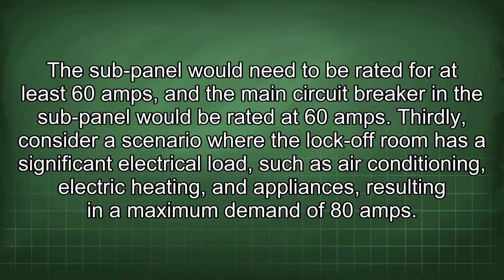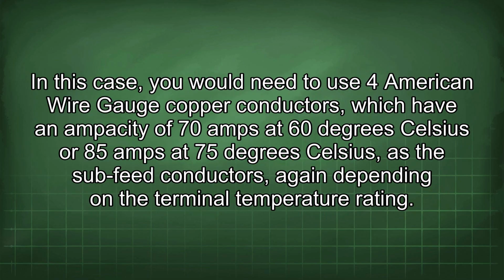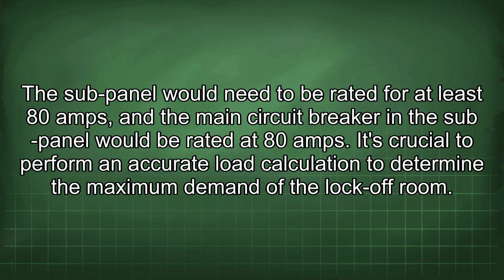Thirdly, consider a scenario where the lock-off room has a significant electrical load, such as air conditioning, electric heating, and appliances, resulting in a maximum demand of 80 amps. In this case, you would need to use 4 American wire gauge copper conductors, which have an ampacity of 70 amps at 60 degrees Celsius or 85 amps at 75 degrees Celsius, as the sub-feed conductors, again depending on the terminal temperature rating. The sub-panel would need to be rated for at least 80 amps, and the main circuit breaker in the sub-panel would be rated at 80 amps.